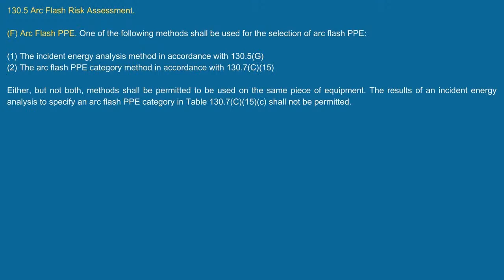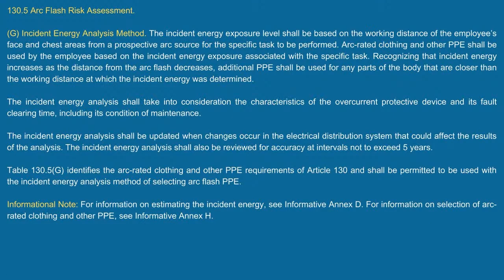True. And one thing I want to ask, based on Nicholas's question. Mm-hmm. This is a really good question, but let's just say, is there a way that the evaluation of the total available fault current could change based on the clearing time of the equipment that you're working on while energized? Hell yeah, it can. The quicker the clearing time is, there's not going to be as much duration there. Therefore, the arc's going to clear quicker, and your exposure to a higher arc rating won't be available. Now, I'll tell you something that a lot of facilities have done over the years.